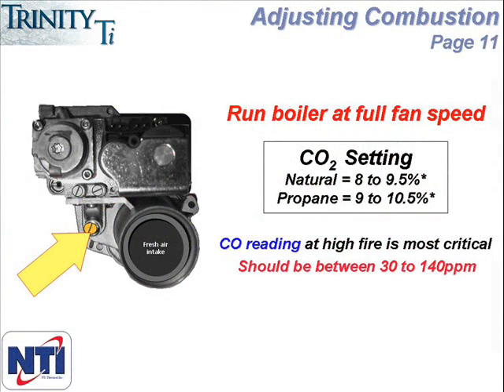NTI recommends performing a combustion test on every installation. It is mandatory when a unit has been converted to LP or when a unit is being installed at altitude, but it's good practice to perform a combustion analysis on every install, and in many areas the local codes require it.